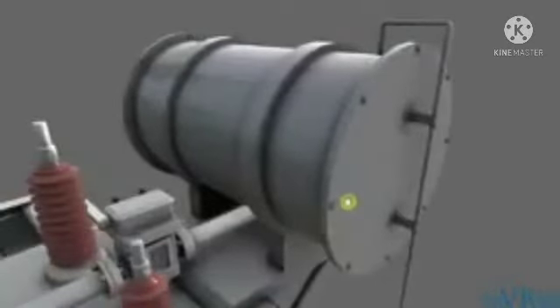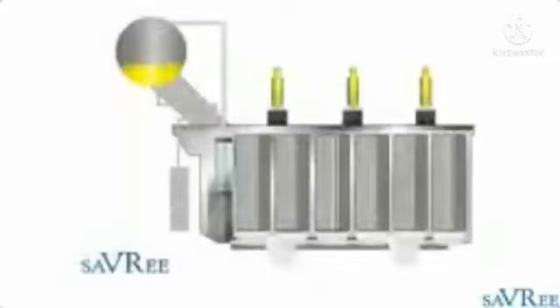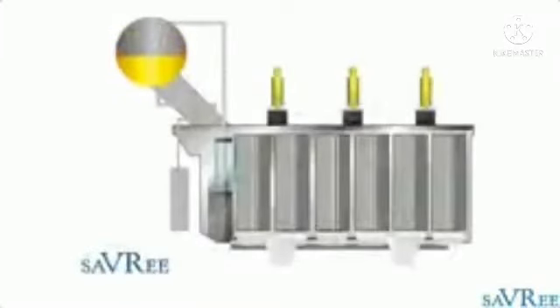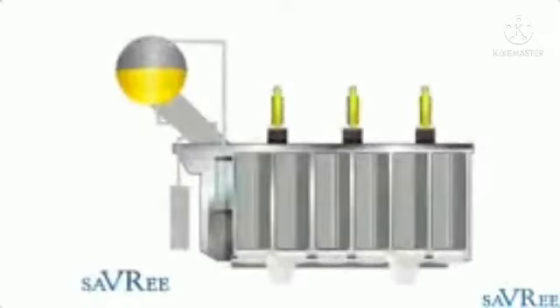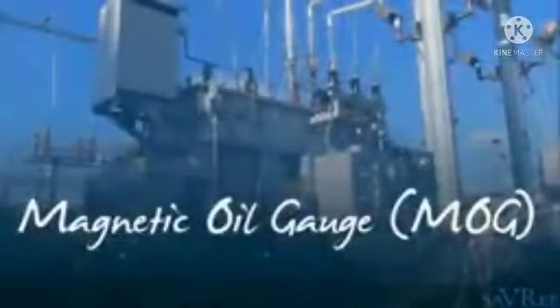Let's go over to our conservator tank again. The conservator tank is installed to allow for expansion of the insulating liquid when it gets heated up or when it cools down. If the transformer is heavily loaded, then the insulating liquid is going to heat up and it's going to expand upwards. When the transformer cools down, the insulating liquid is also going to cool down, and then the insulating liquid level is also going to drop. So as we heat up the insulating liquid, it's going to expand, and as we cool it down, it's going to contract. In order to know what the level is, we install a MOG, and this is a magnetic oil gauge.